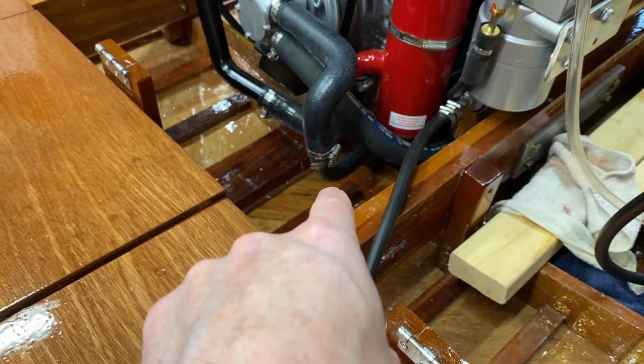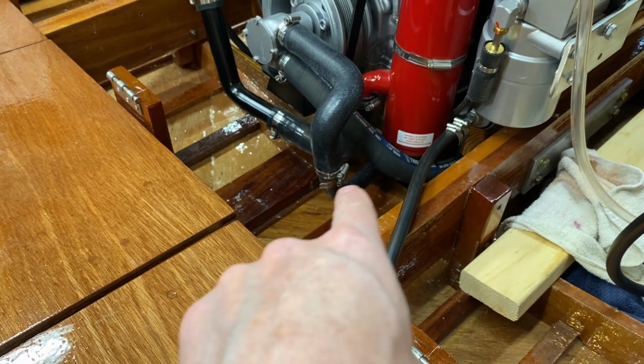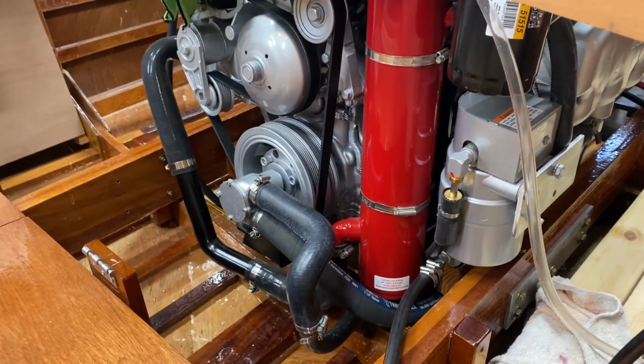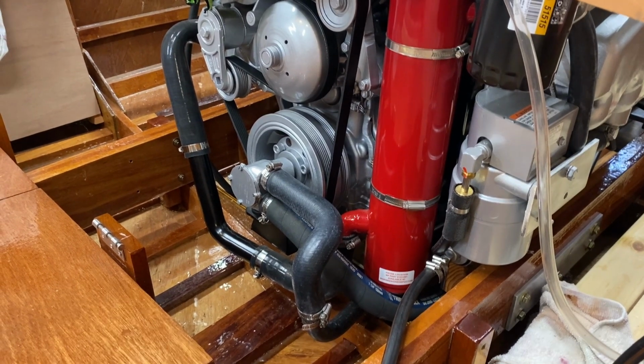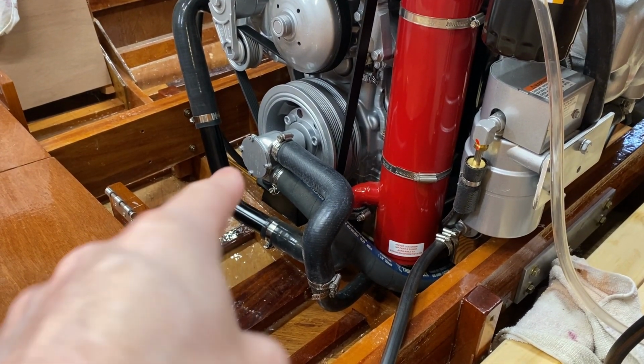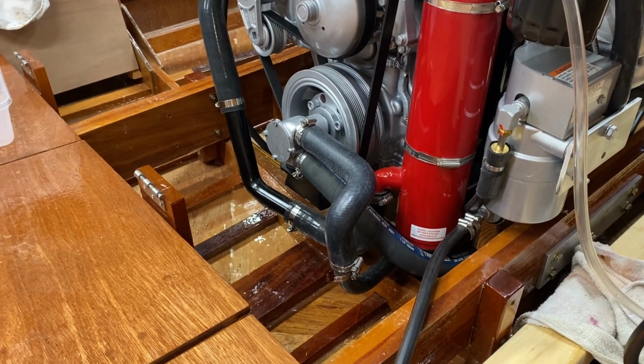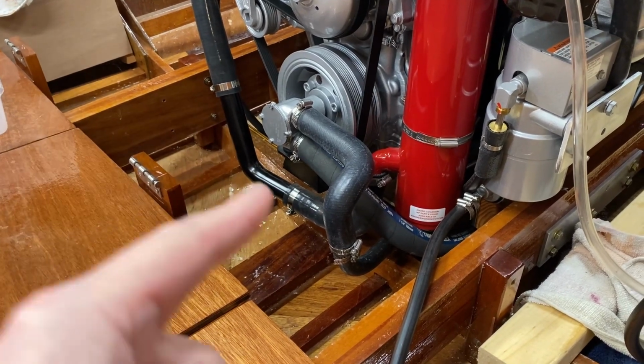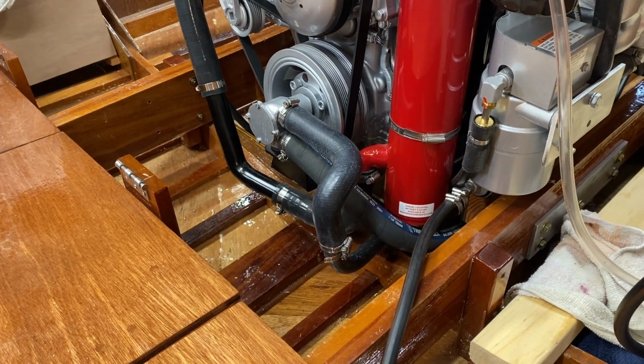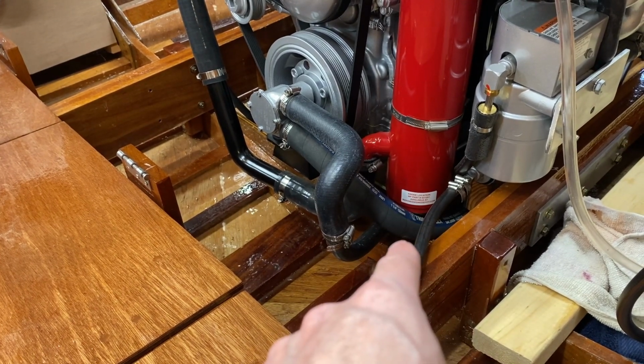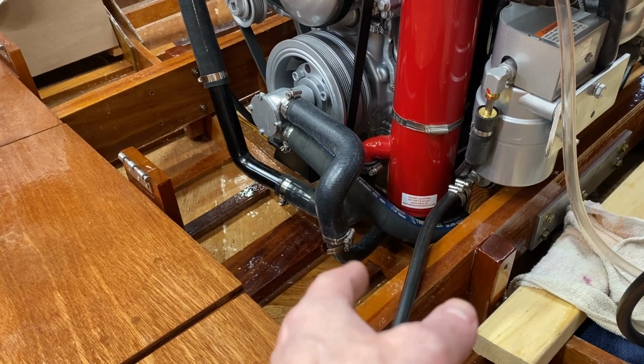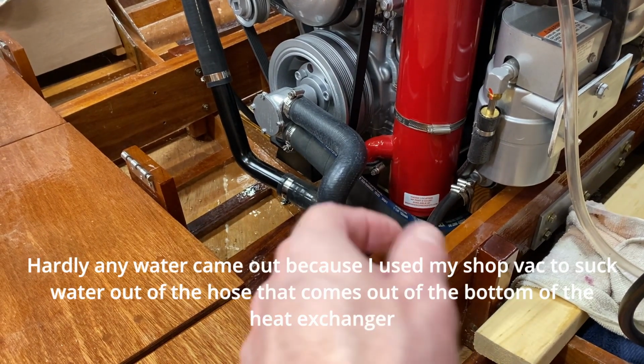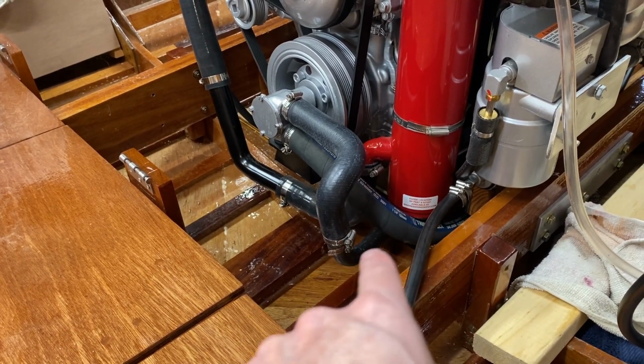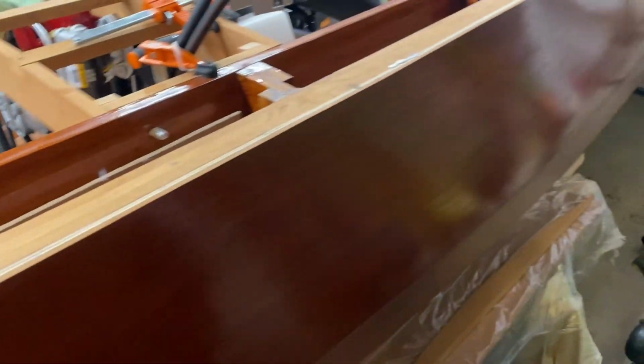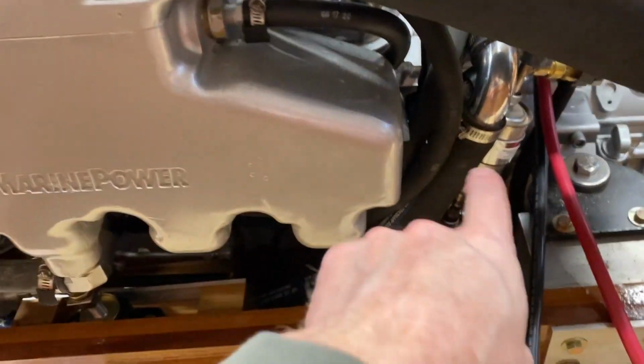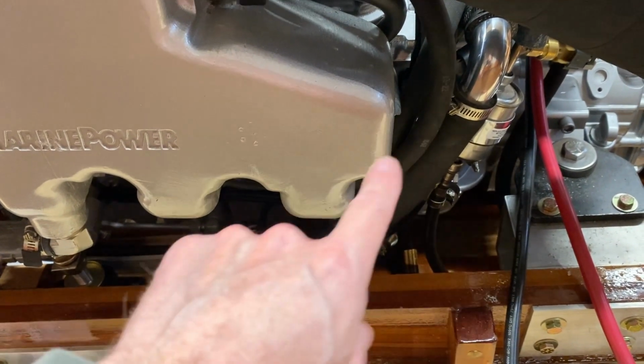Then take the shop vac and suck out that small hose going to the bottom of the heat exchanger. What I actually did too is take that cap off and make sure that was drained out good, then take a pipe cleaner and make sure there was no residual water between the vanes of the impeller. There's also that little valve at the bottom of the heat exchanger—unscrew that, and hardly anything comes out. Screw that back on, then put a little RV antifreeze in here, the bottom of that short hose, and pour some in here too, so it sits in that hose.